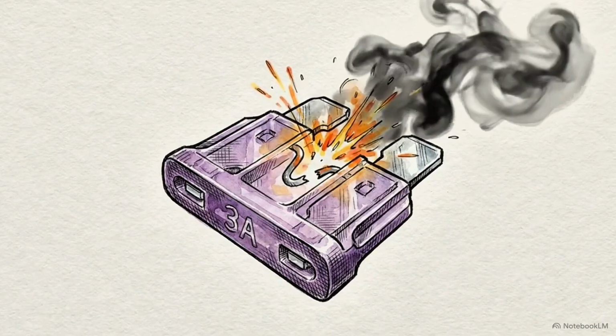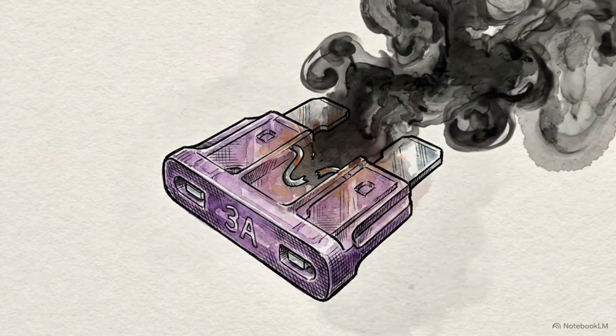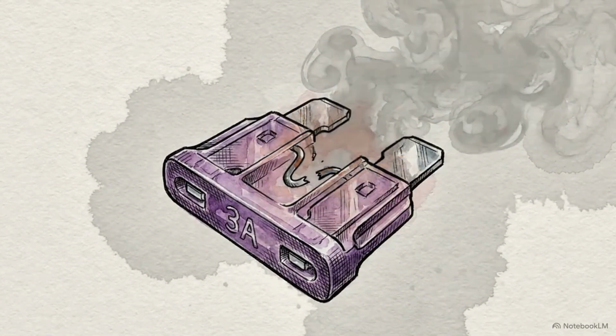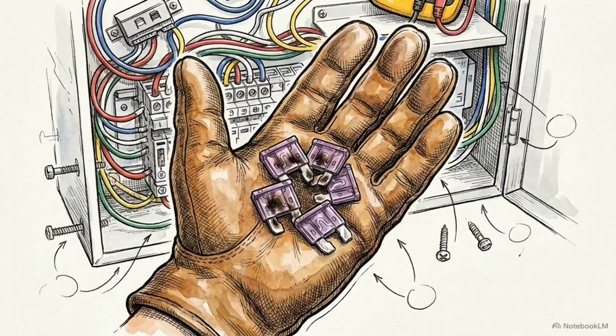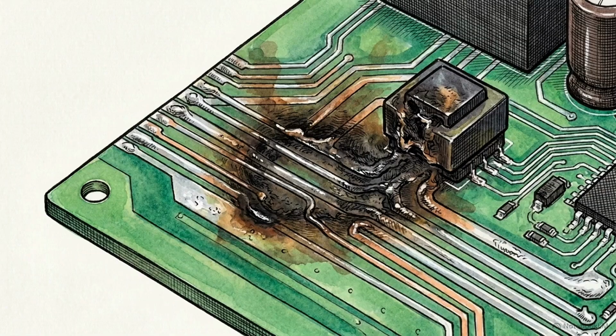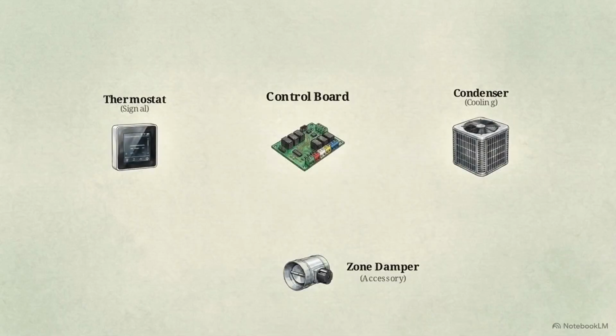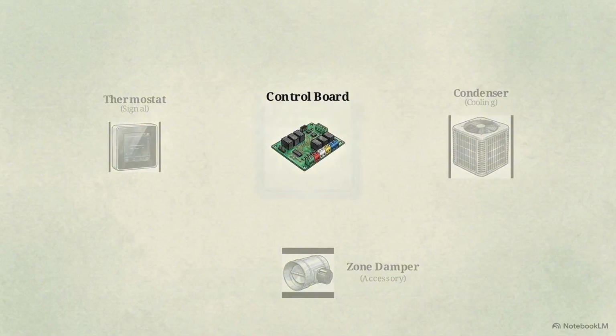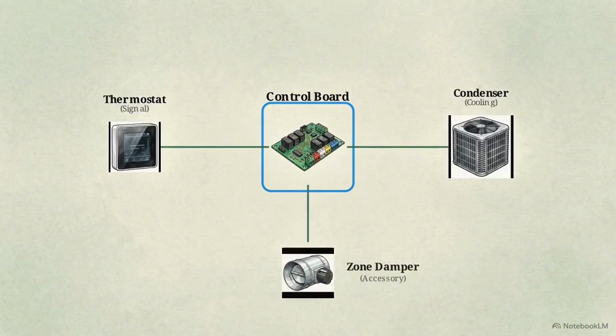You replace the blown 3-amp fuse, you power the system back up, and the new fuse pops immediately. Pushing another fuse into the board to see if it holds is a guaranteed way to waste time. Worse, repeatedly sending high-current short circuits through the system stresses the transformer and can permanently damage traces on the main control board. Instead of swapping parts by trial and error, we isolate the short circuit by disconnecting specific segments of the system, verifying the voltage, and testing individual branches.